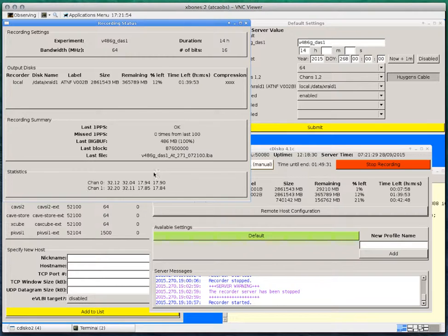Generally I wouldn't bother correcting for this, but when they get much worse I would. If the nominally 17% value is too high, that means there's too much power going to the system, and you need to reduce the gain. If the nominally 17.3% value is too low, you need to increase the power, so increase the gain.